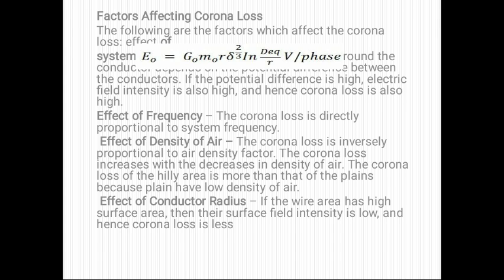Some factors affecting corona: system voltage, effect of frequency, effect of air density, and effect of conductor radius. Corona loss is directly proportional to the system voltage, directly proportional to the frequency, inversely proportional to the air density factor, and inversely proportional to the distance between the conductors. These are some of the factors which affect corona.